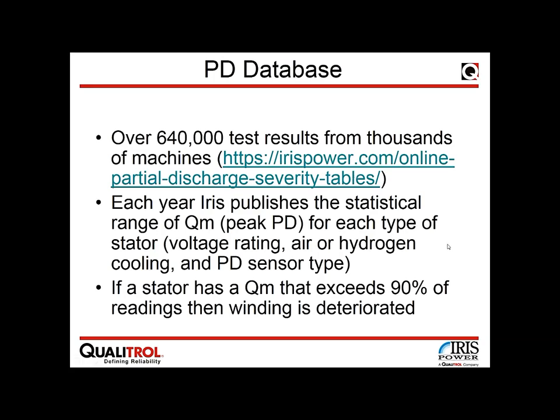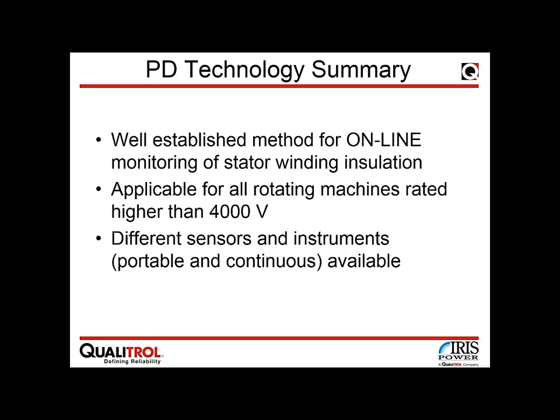Since there is no standard regulating how much PD is too much, the severity tables serve as a useful guideline. After the first test, a user can immediately determine whether their machine falls in a high-reading group or an average PD results group. Partial discharge technology is well established, having been used for 55–60 years in various forms, and is applicable to rotating machines rated higher than 4000 volts.